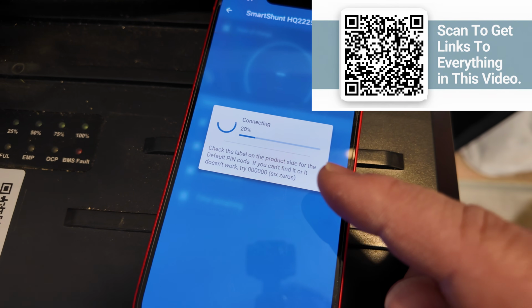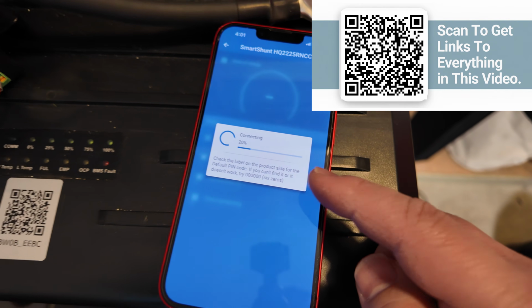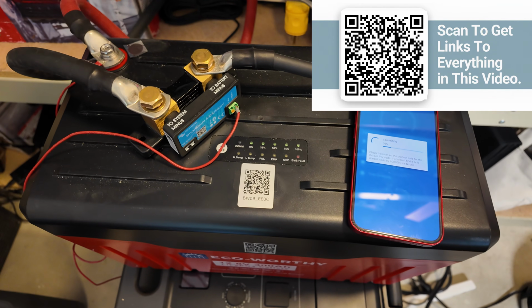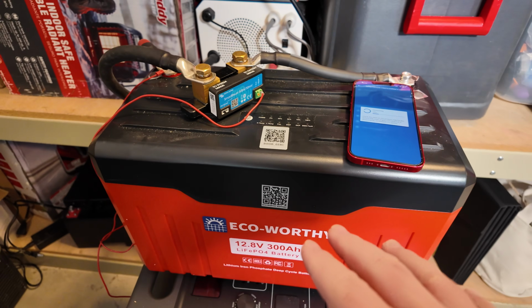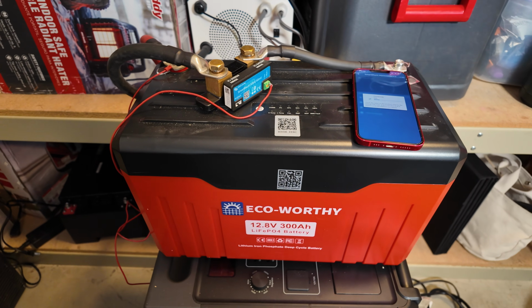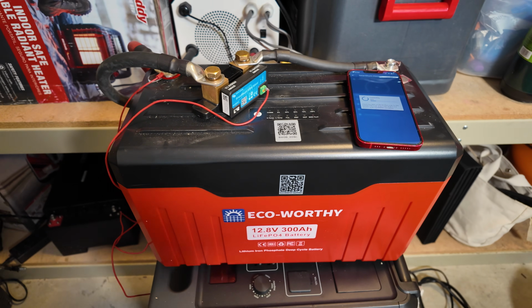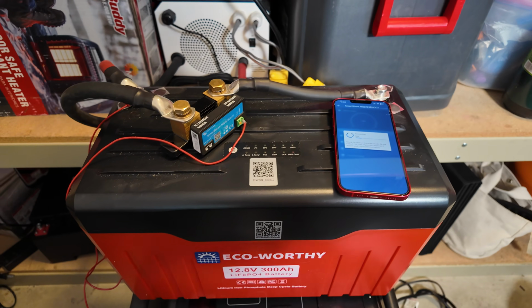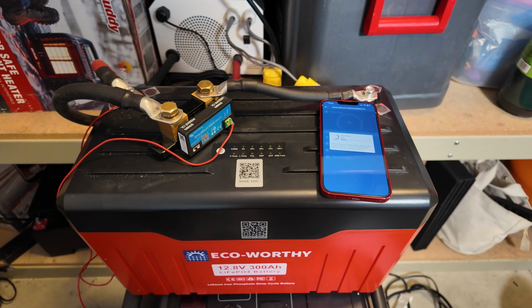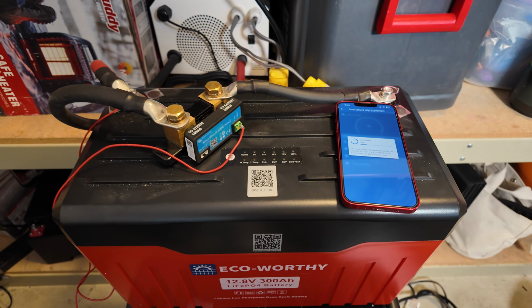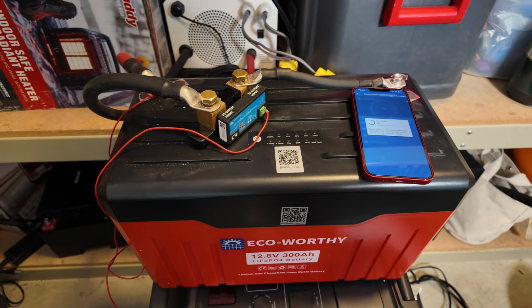We lost connection here on the shunt, which means the battery is the one that shut down. That's actually great to see. This does have overcurrent protection built into the BMS programming. It shuts down if you exceed its 200 amp rating by a fairly decent margin, and it reacts pretty fast too.